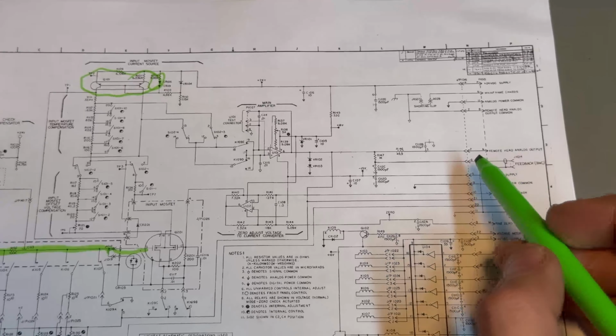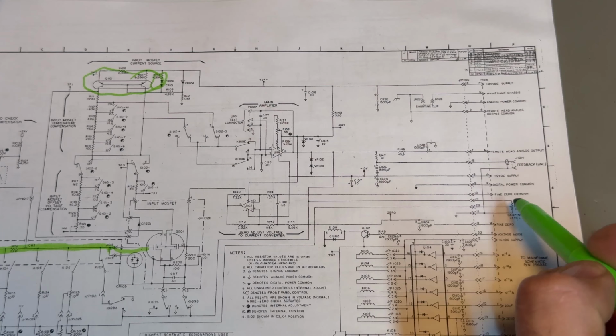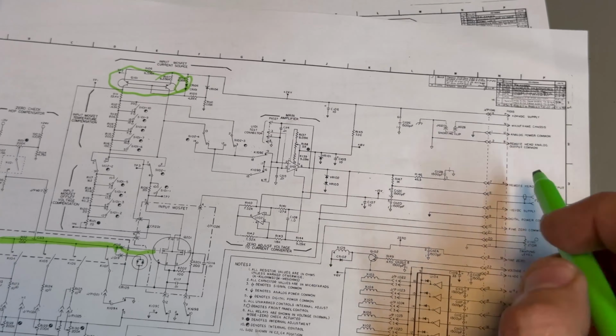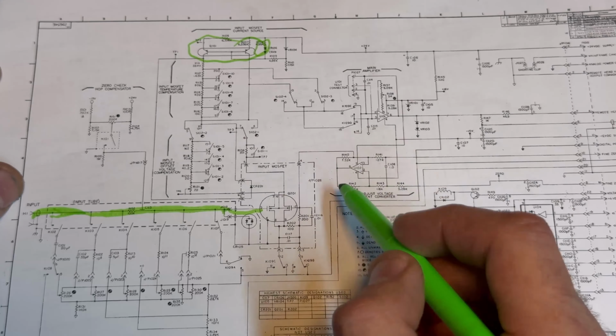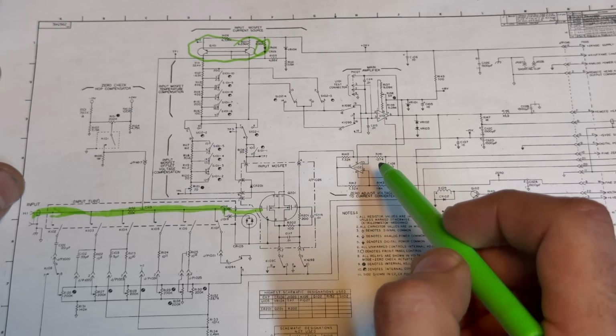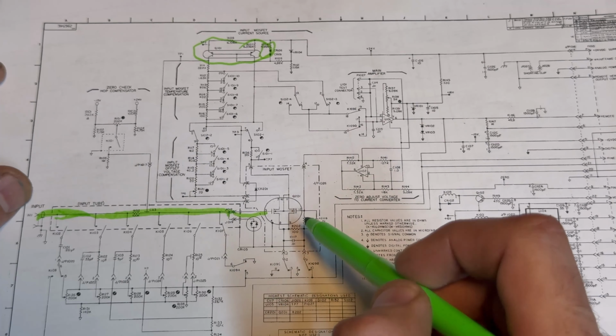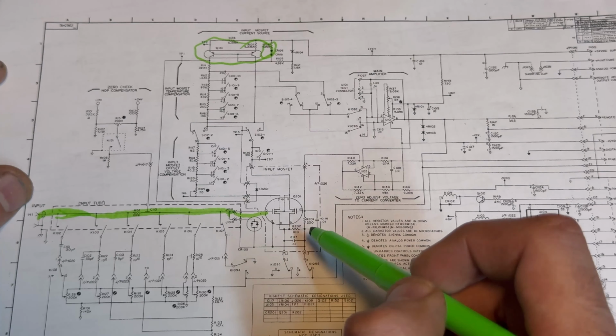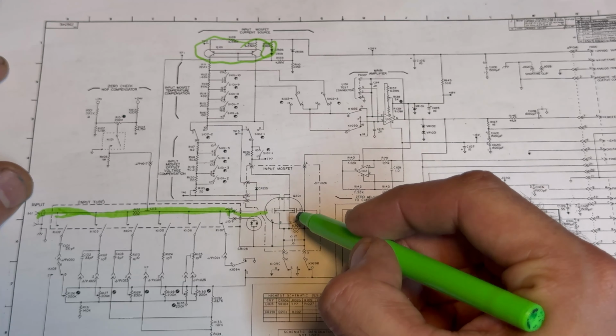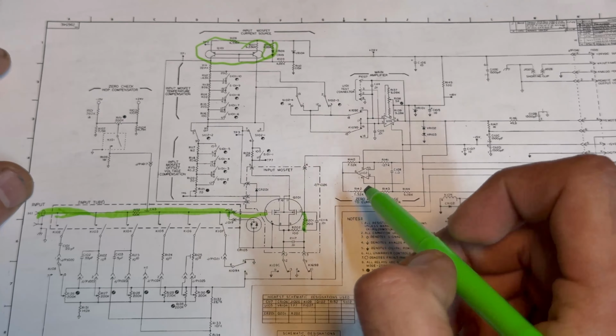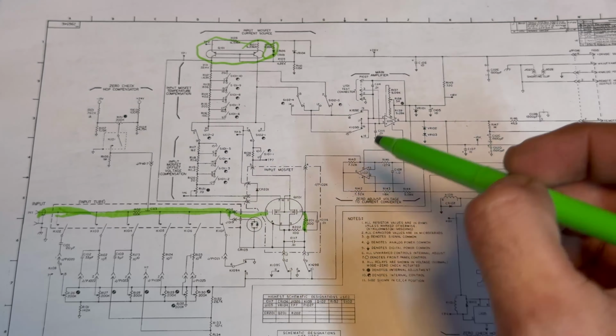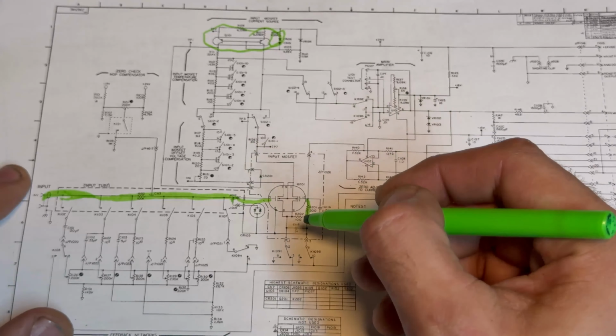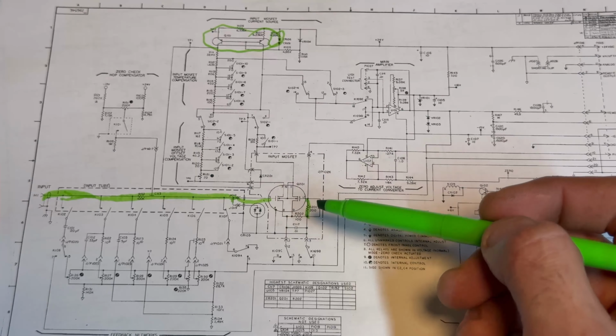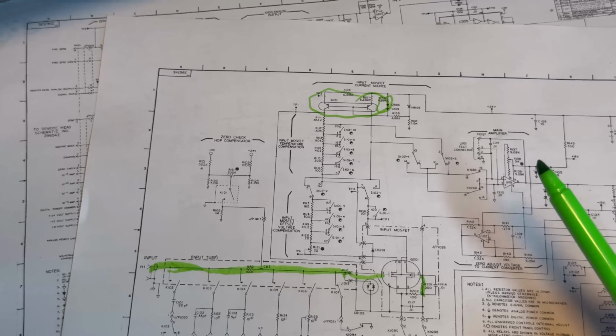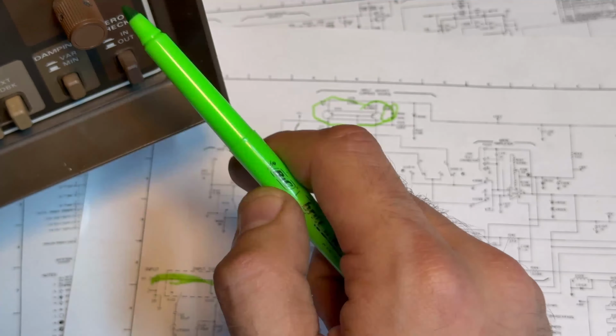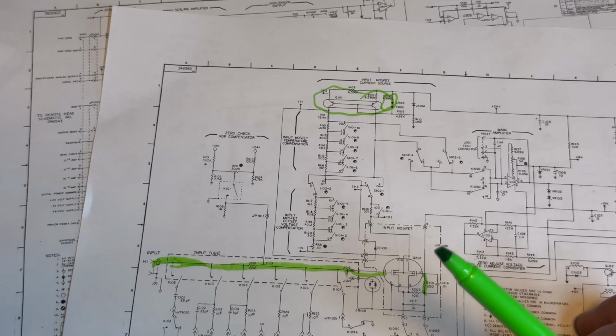The offset trim, there's a very fine zero. There's a fine zero, which is a voltage to current converter circuit here that puts a current into this node, which generates a voltage across R201 here. And this R201 has the job of compensating the last remaining offset voltage. This is the control that's on the front panel. It's this here. It's a trimmer. It's a multi-turn potentiometer.